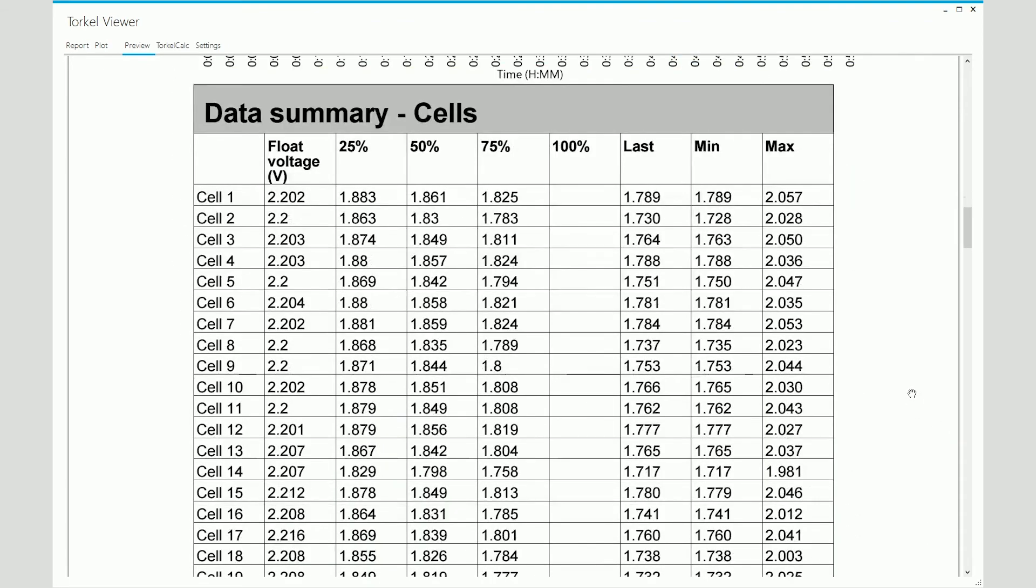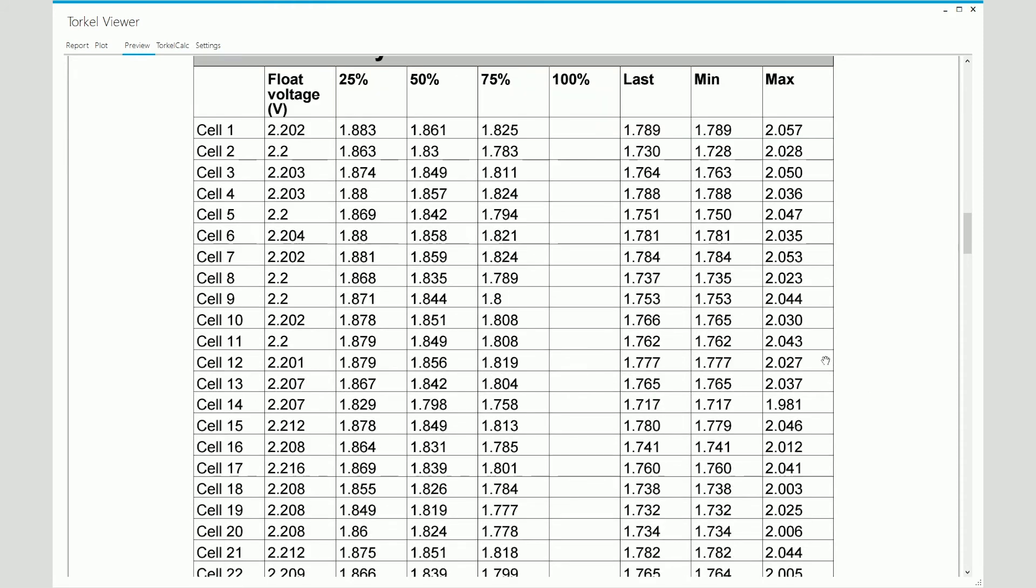Below that, since we checked the include BVM summary data checkbox, we see a summary of the BVM test data in a tabular format. We see the float values. Again, we see the 25%, the 50%, 75% values. We do not see the 100% values for the same reason. The test was stopped before the intended duration was completed because the battery reached its end voltage before the one hour mark. The last recorded values are shown. And over here, you see the minimum and the maximum values recorded on each cell during the course of the test.